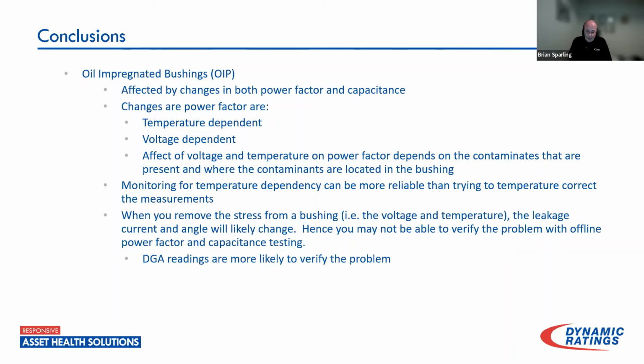The other thing is that when you remove the stress from the bushing, in other words, you take away the applied voltage and temperature, the leakage current and phase angle will change.